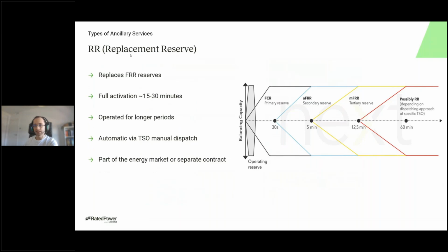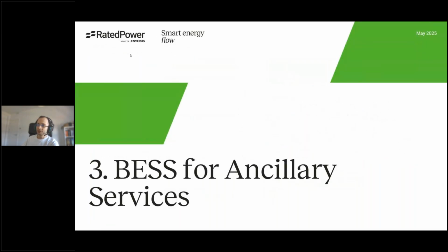And finally, we have the replacement reserve. The idea here is to replace all the FRR and FCR that have happened before. It takes longer to activate, normally 30 minutes, but it can be a bit faster. It can be operated for a long period of time. Also manually activated by the TSO, and it's typically part of the energy market, or there are some ad hoc separate contracts for it. So this is for frequency regulation, and now let's see what is the role of batteries in all of this.